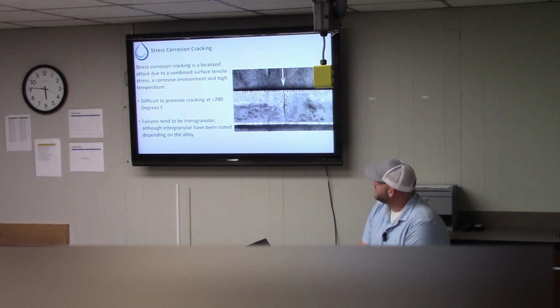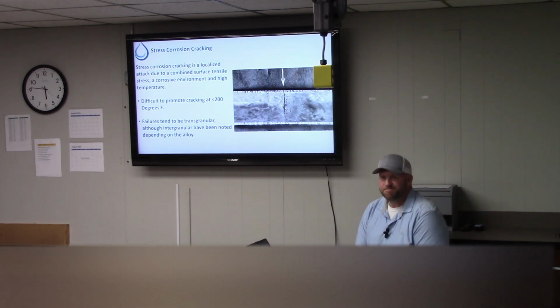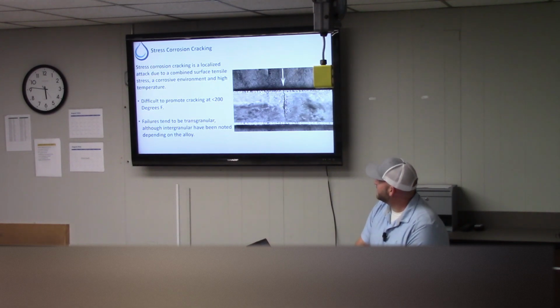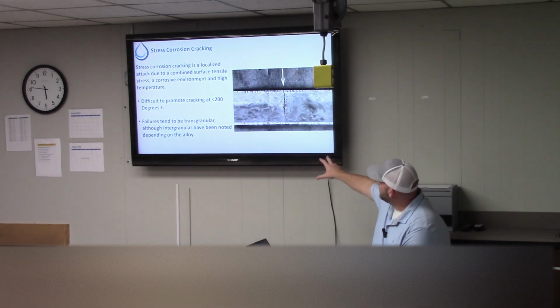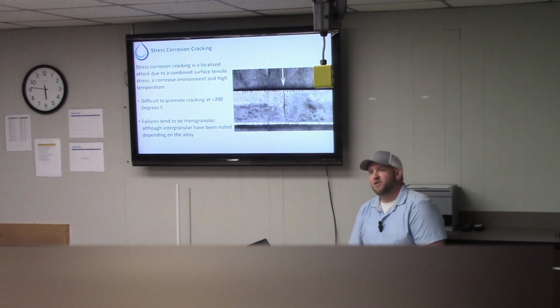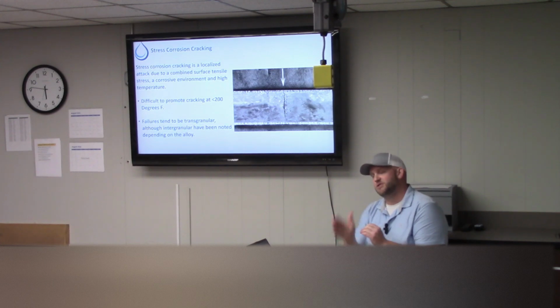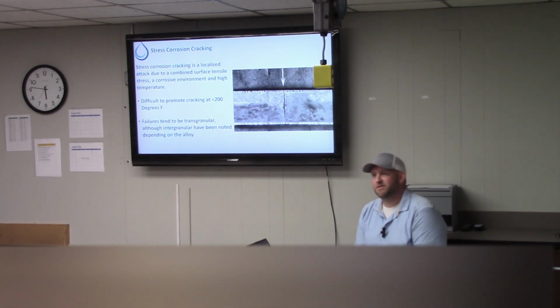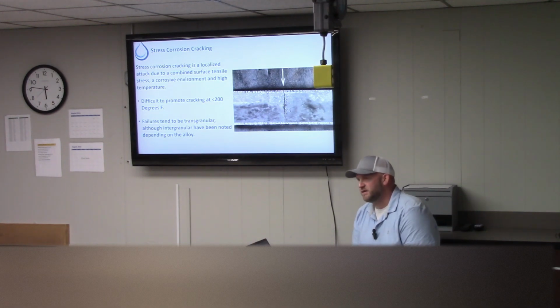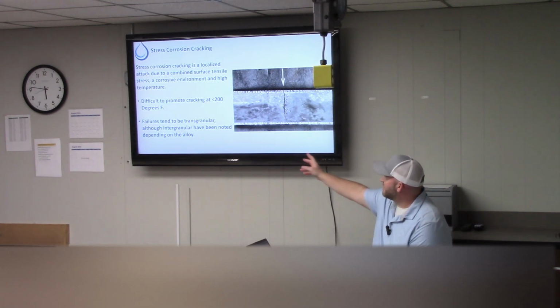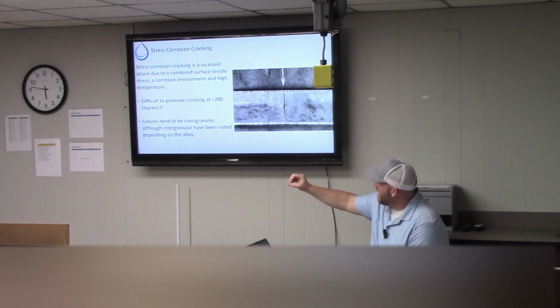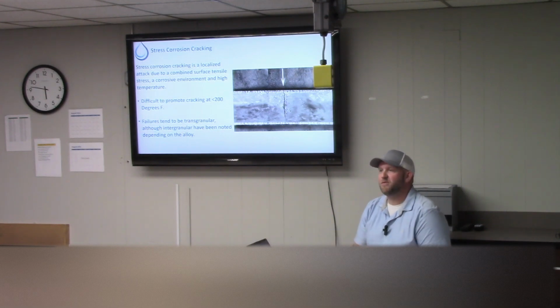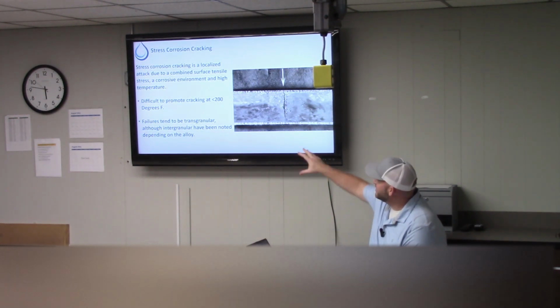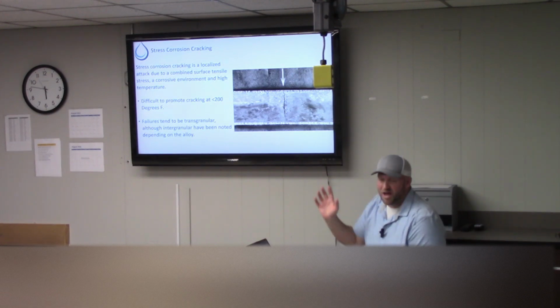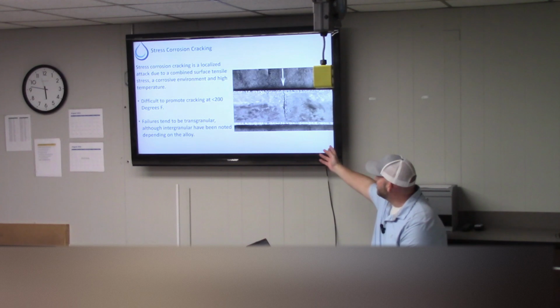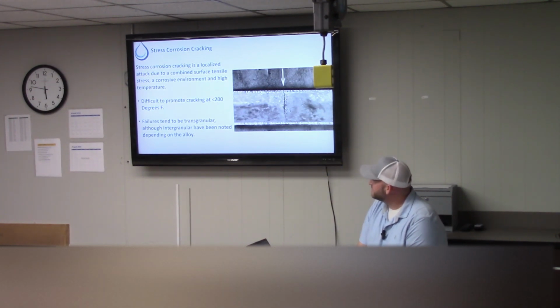A little bit of vibration and too many chlorides does not a summer make, and this is a perfect example of that. In failure analysis, we'd be very interested to know if the crack occurred transgranular or intergranular, which would give us an idea of why it failed. If you have the right temperature, the right amount of vibration, and too many chlorides in your system and not enough of the correct treatment, you'll be susceptible to this in all your systems.